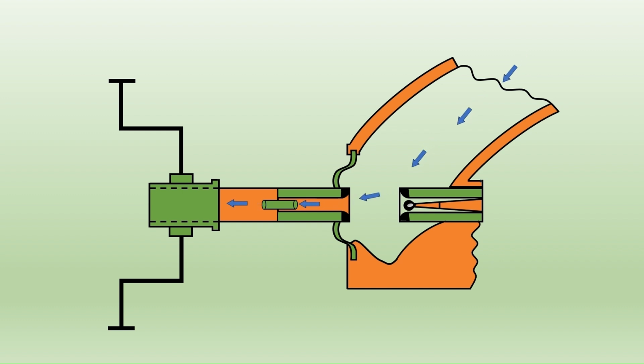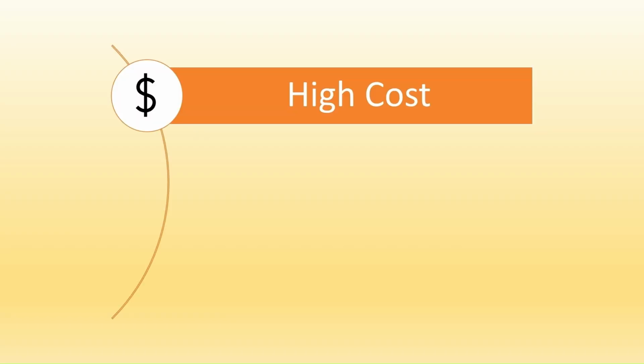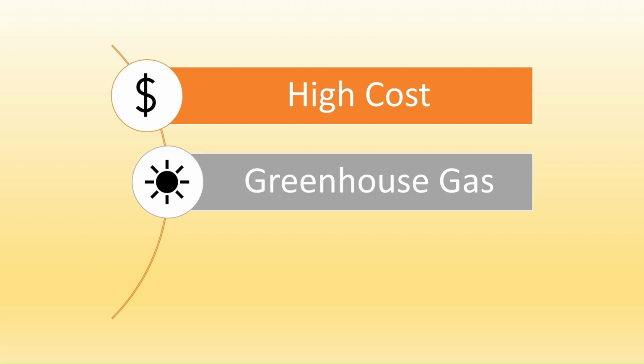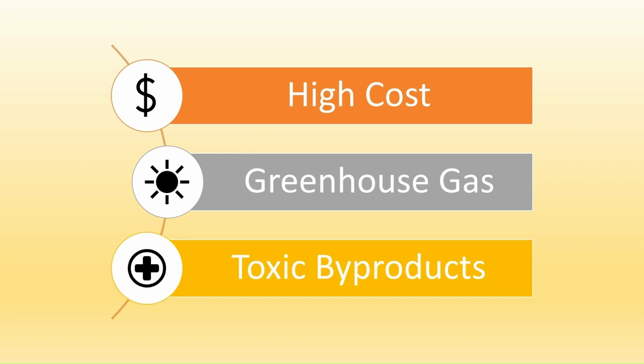Apart from all the benefits of SF6 gas, there are certain disadvantages. SF6 gas itself is expensive, and the specialized equipment needed to handle it and the breaker's complex design contribute to a higher initial cost compared to other types of circuit breakers. SF6 is a greenhouse gas with a high global warming potential. If it is released into the atmosphere, it will contribute significantly to climate change. During arcing, SF6 can decompose into toxic substances like sulfur dioxide, which can irritate the respiratory system and skin.